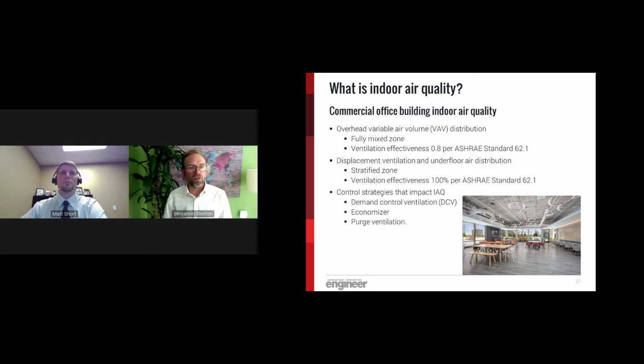When we look at commercial office buildings, demand control ventilation is one of those. Demand control ventilation controls the ventilation based on occupant demand. And the way that we see occupant demand is through CO2, or carbon dioxide. There aren't really any other sources in buildings that introduce carbon dioxide levels. So it's a very good indicator of how many people you have in a space or within the building. This is best and most effective on the zone level. For instance, if you have a conference room and the CO2 levels get very high very quickly, you're going to want to bring more ventilation into that through your automation system.